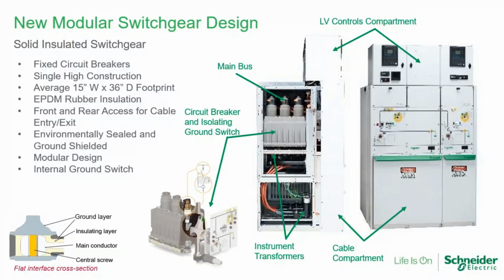They have both front and rear access designs, but we do have designs that are available for front access only. So if you need to put it up against a wall, very similar to the gas insulated switchgear, those are optional. Environmentally sealed, very similar to the gas insulated switchgear. All of the electrical components, all the current carrying components, as well as all of those moving components of the circuit breaker and internal disconnecting grounding switches are sealed away and environmentally sealed from all those contaminants that we talked about before, either in the solid insulator itself or inside of a solidly insulated circuit breaker tank. And again, solid insulated switchgear has the modular design built in with it. So it's very easy to lay out and design an entire lineup of solid insulated switchgear. If you look at the circuit breaker in the bottom left, it looks very similar. You're still going to have vacuum bottles or vacuum poles for the actual interrupting and an operator mechanism in the front of it.